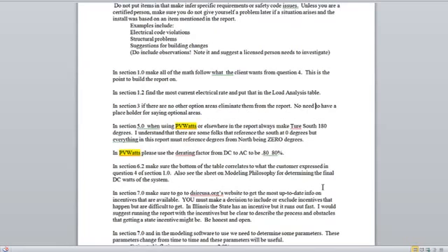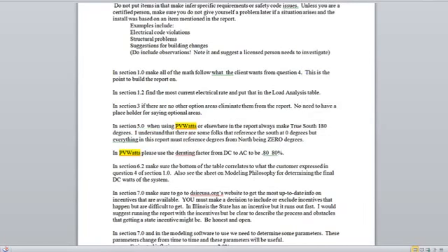When you use section 5.0, we like to use PVWatts, which is through the Department of Energy website. So it's an open source energy calculator. Here's the thing that you need to make sure of. We want to make sure that it is facing true south. Now, I understand that some of us in solar thermal systems will talk about using a financial calculator, and they will make south 0 degrees because everything needs to point south in order for it to work. For our report here and for PVWatts, make sure that the angle is 180 degrees.